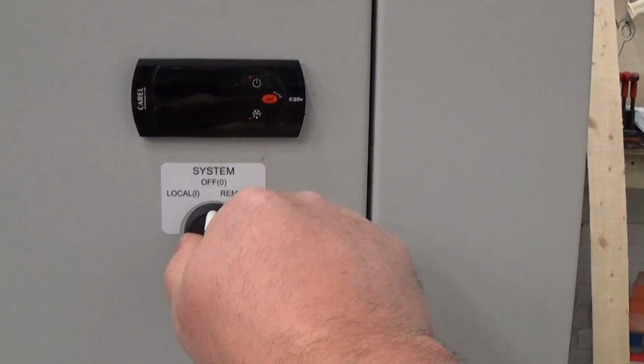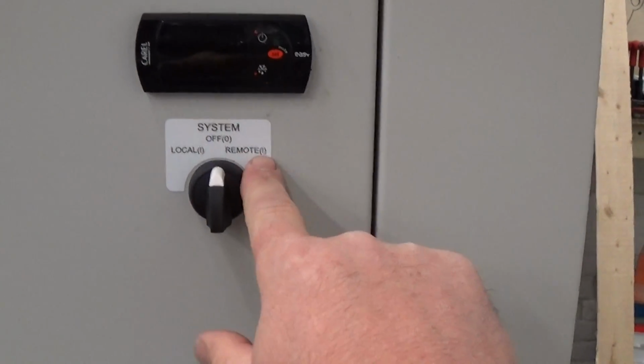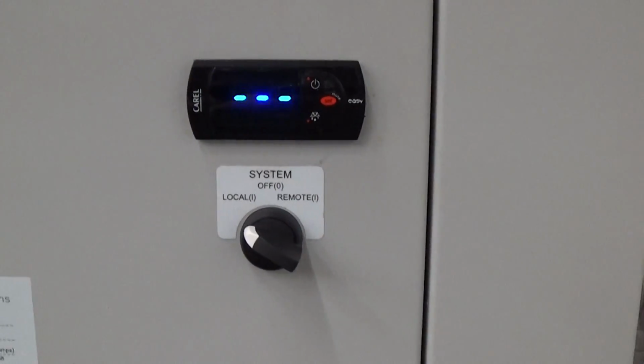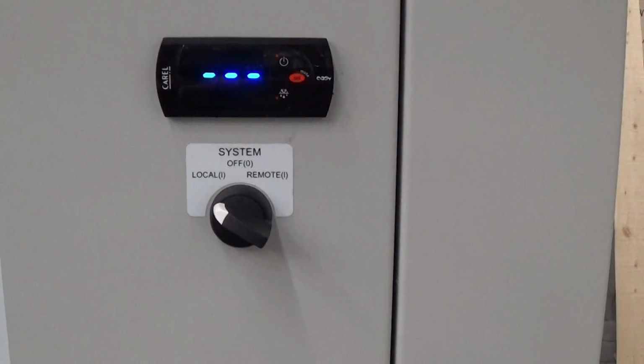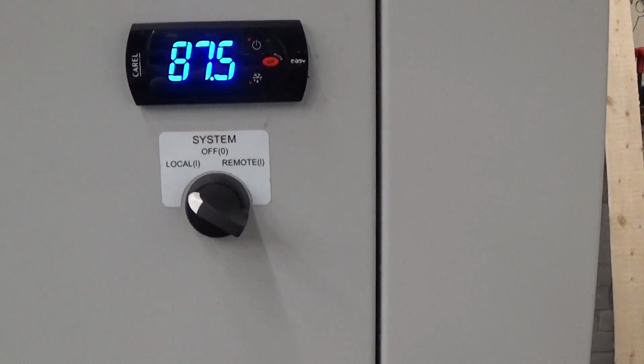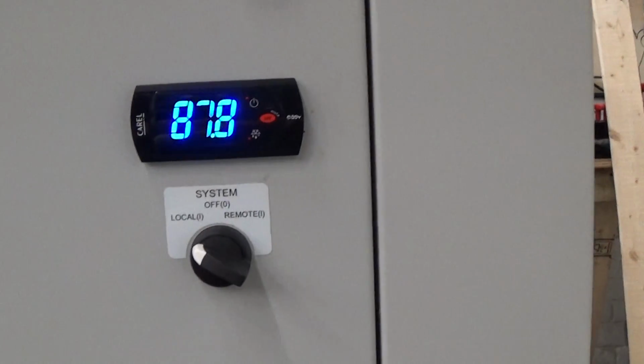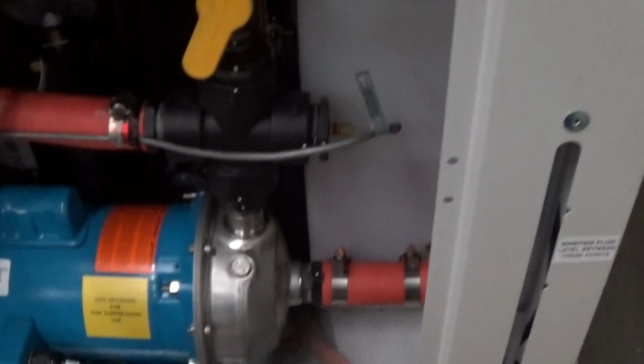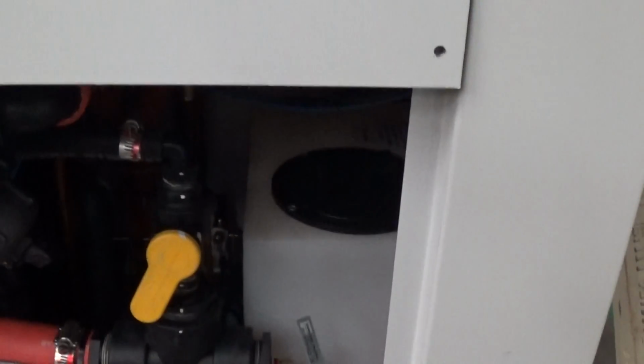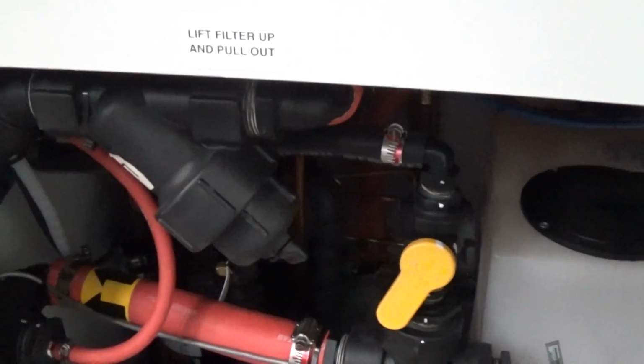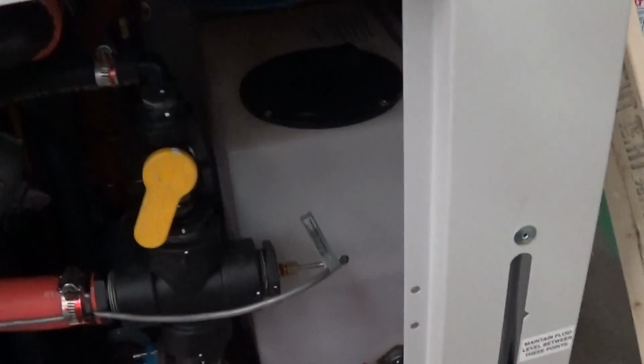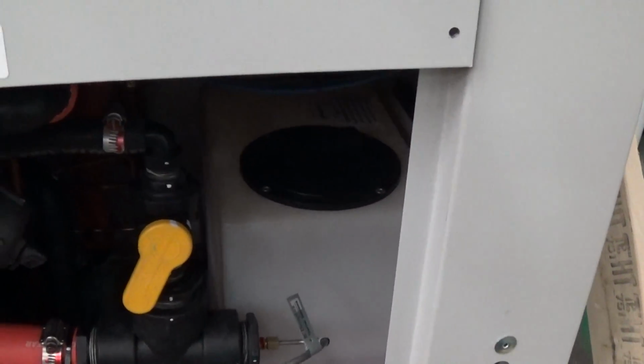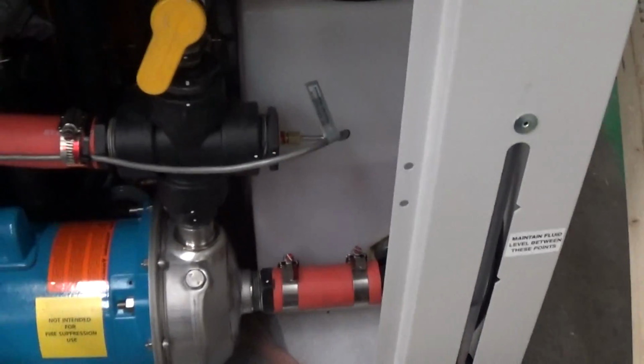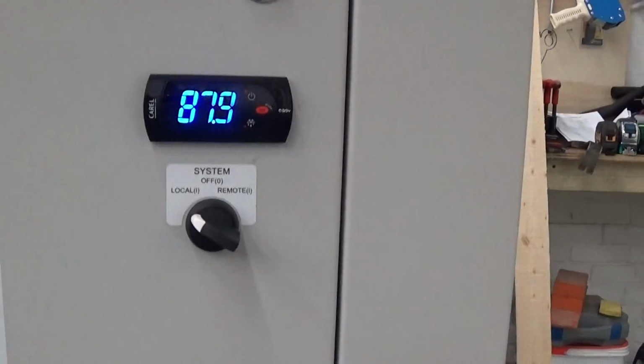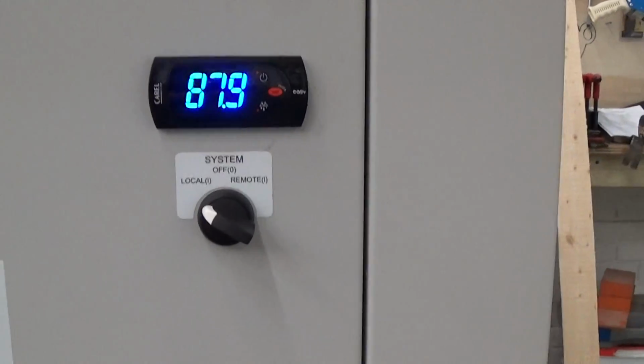To turn the unit off, you can just use this selector switch and put it in off. We're not using remote. We just put it on local. The second we put it on local, the pump does power up. Real simple controller here. We have the tank heated up to 87 or 88 degrees right now. Because this unit is configured for a 30 or 32F set point, we're running glycol, and the customer's going to have to run glycol too. About 30%. I wouldn't go any more than 30%. That gets a little bit too thick for a chiller of this size to be pumping fluid.